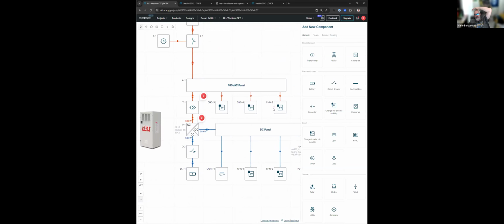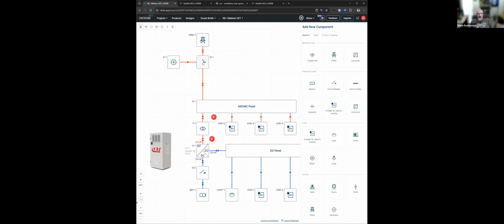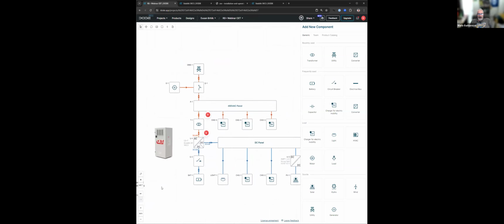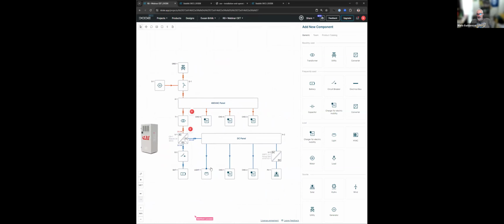The only thing here is that you need to balance your load, and the zigzag will allow you to do that by taking about a third of the current of each phase, and by doing so, you'll be able to balance the phases that are feeding your AC loads. So that is sufficient to do the job, basically. You don't need the big shebang with all the iron core — that would be overkill for what's required here.